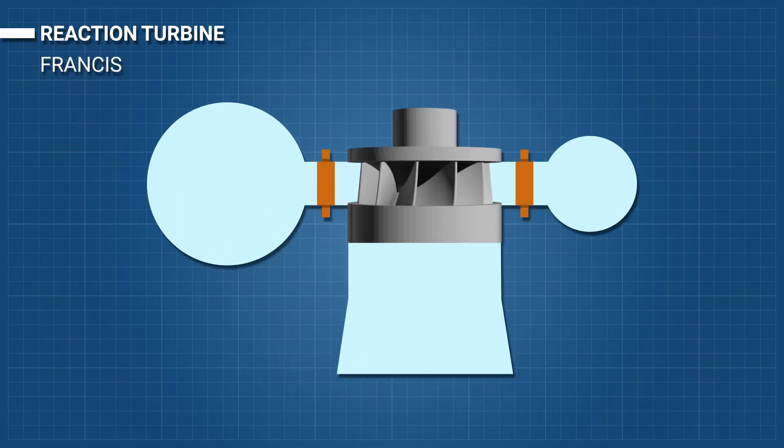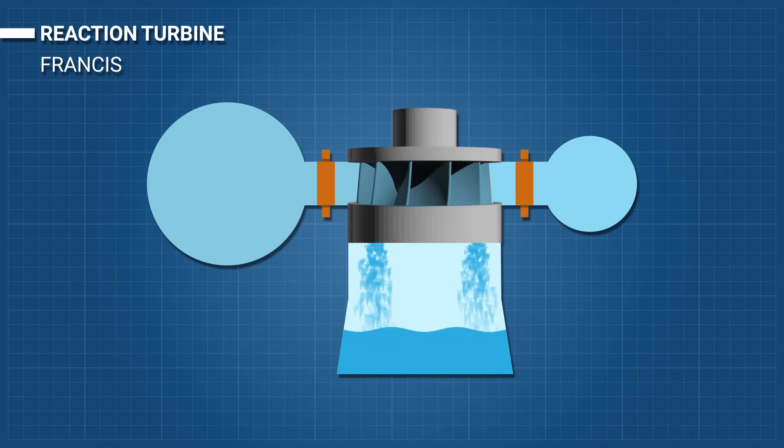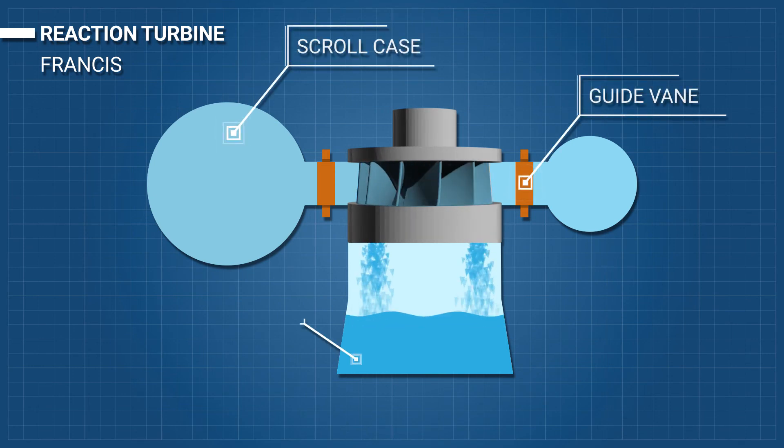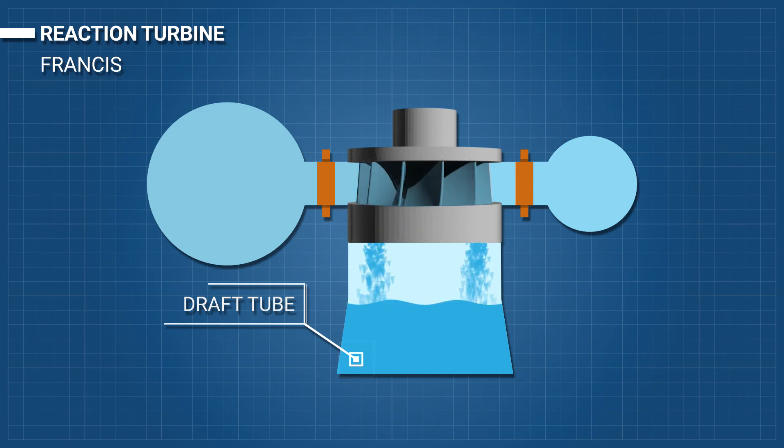Francis: A Francis turbine has a runner with fixed buckets or vanes, usually nine or more. Water enters just above the runner and all around it, and then falls through, causing it to spin. Besides the runner, the other major components are the scroll case, guide vane, and draft tube.